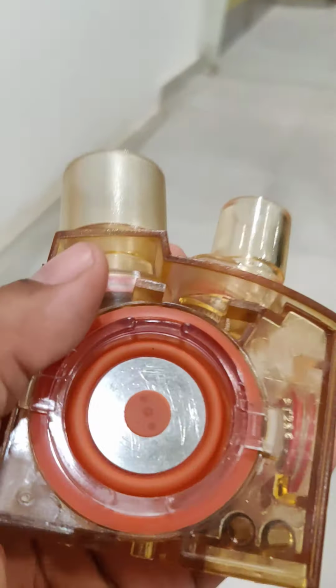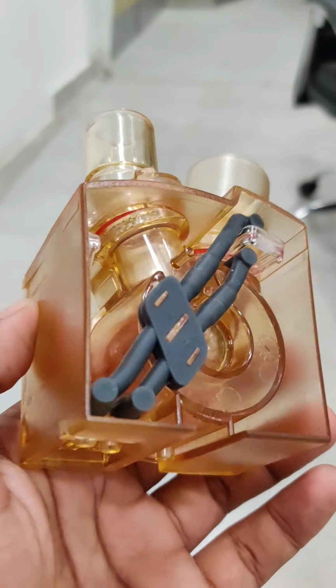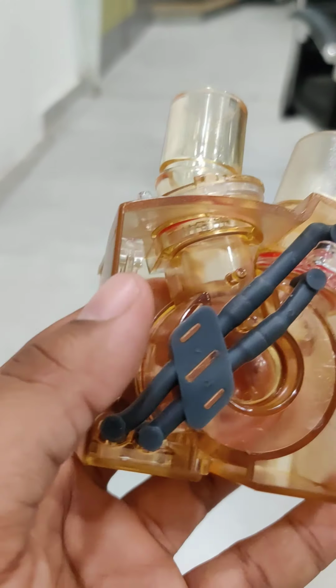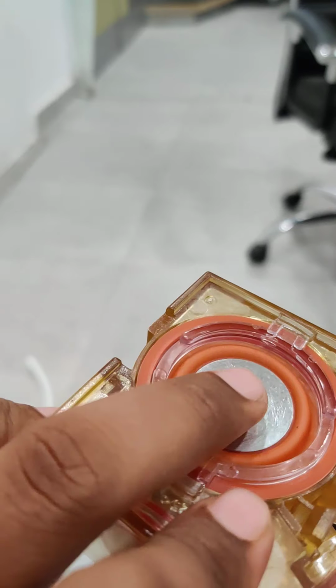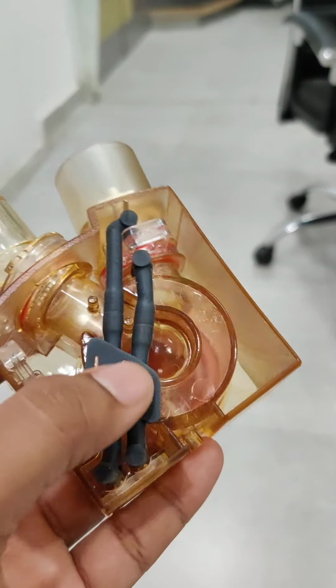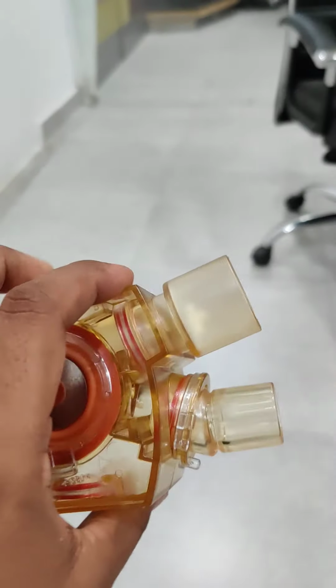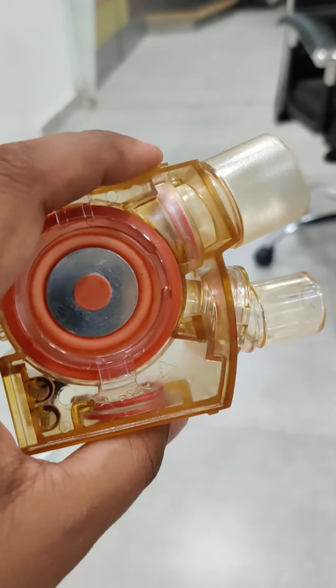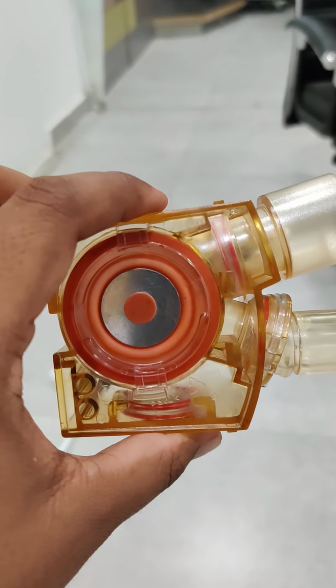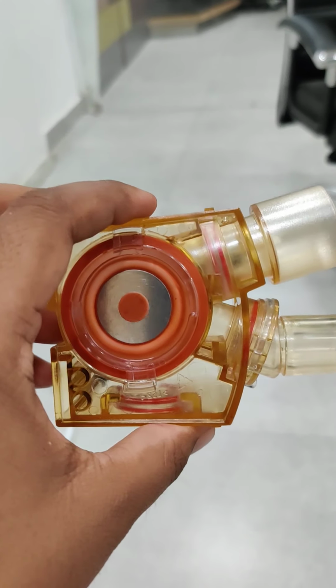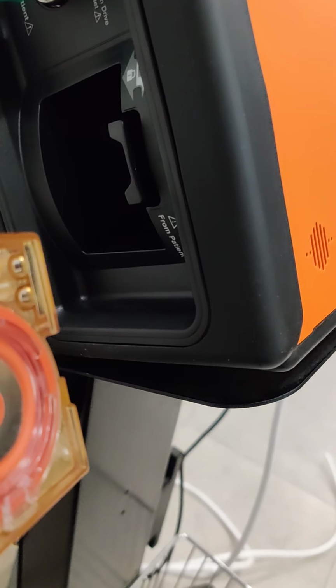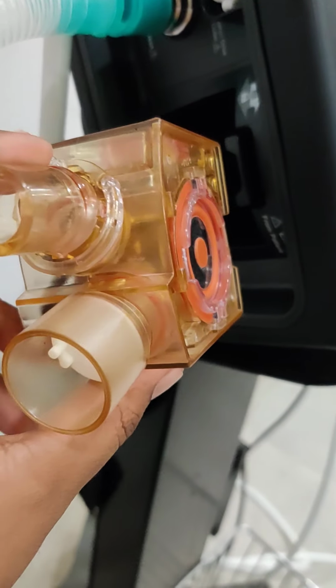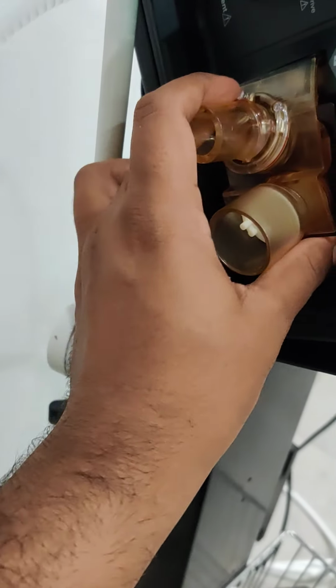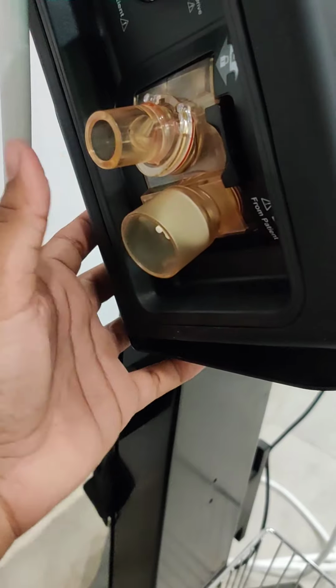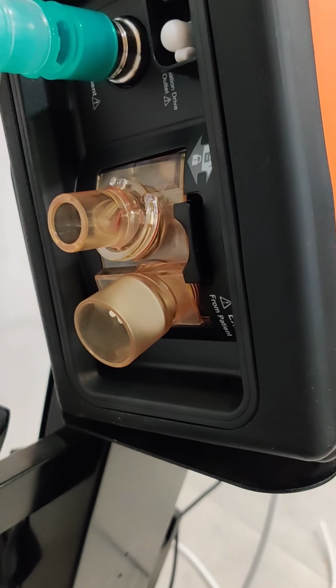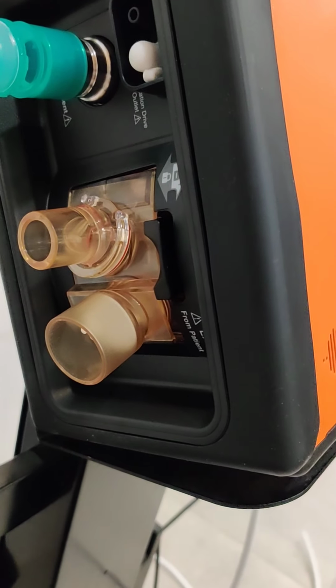This expiratory block is fully autoclavable at 134 degrees Celsius for 20 minutes, provided that you remove this diaphragm from the expiratory block, and these tubing should be removed. Then, if you have any infectious patients, you can autoclave this expiratory block all the time at 134 degrees Celsius. Now for putting this expiratory block back into the ventilator, you just have to push this, and whenever you get a click sound, that means the expiratory block has been locked in the ventilator, and now it is ready for use.